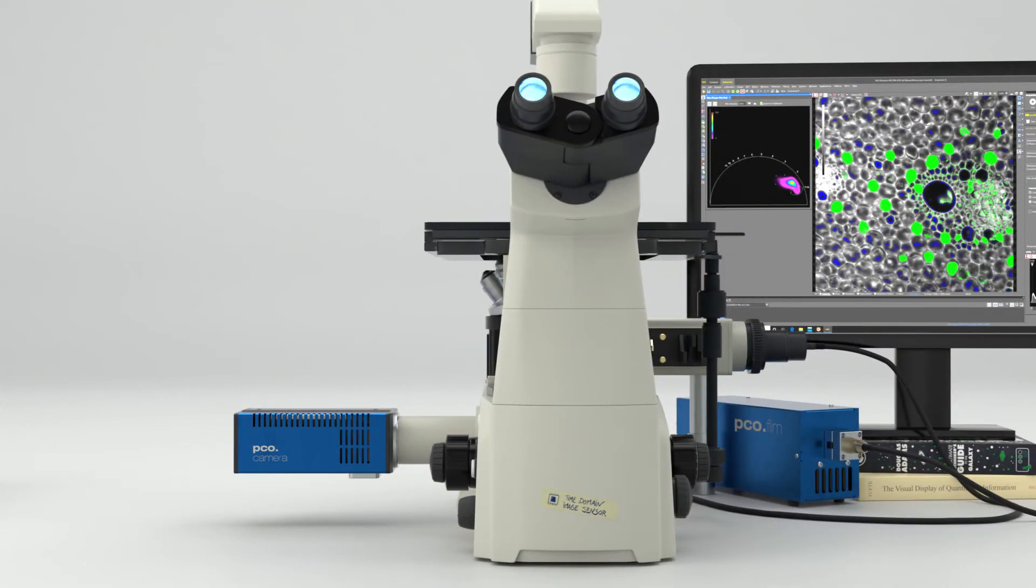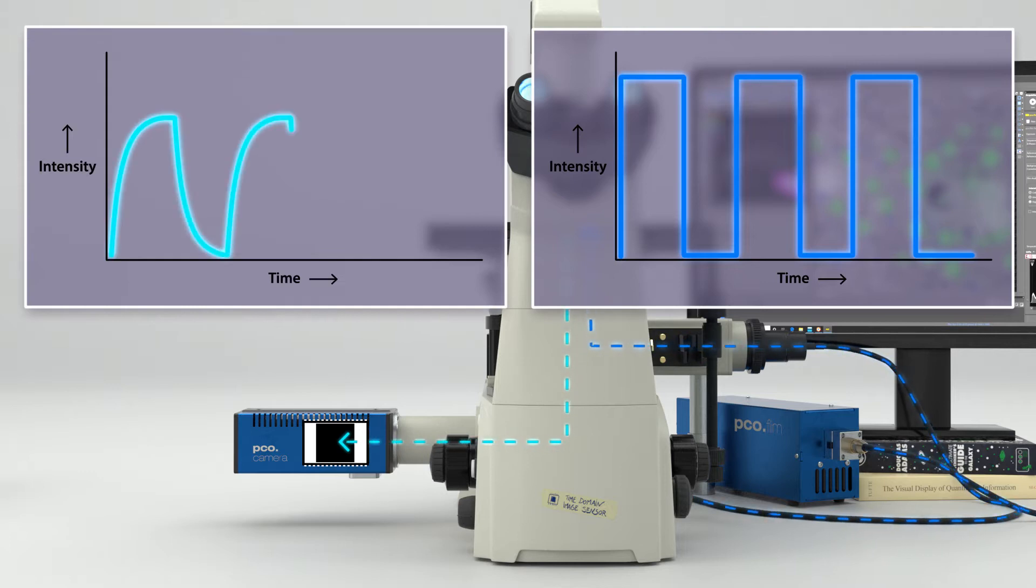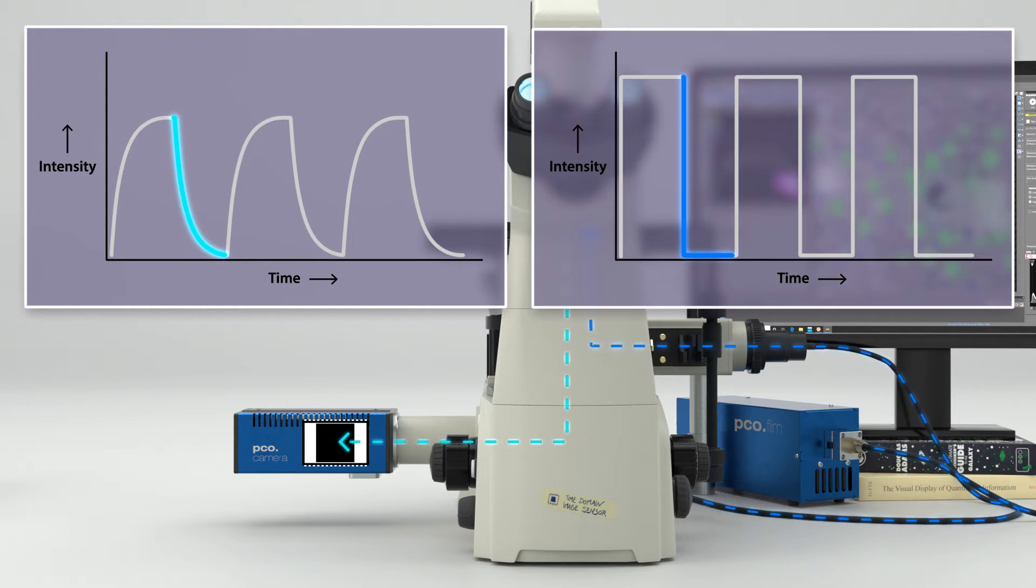Another kind of time domain FLIM uses a digital image sensor. In this setup, the sample is excited by a periodic train of rectangular light pulses. Each excitation pulse results in a slightly delayed, weaker emission signal, starting with a sloped rise of the emission intensity giving the rise time, and a decaying emission after the excitation light has been turned off giving the fall time.